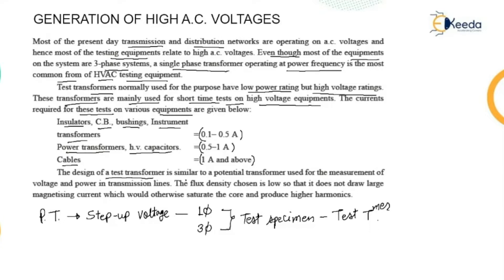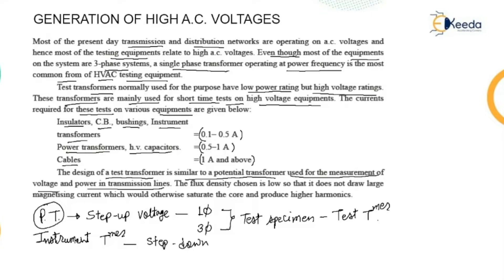The design of this test transformer is similar to a potential transformer used for measurement of voltage and power in transmission lines. In an instrument transformer the voltage is stepped down, but in case of a testing specimen the voltage is stepped up — that is the key difference. The flux density chosen is low so that it doesn't draw a larger magnetizing current, otherwise it may saturate the core with high harmonics.